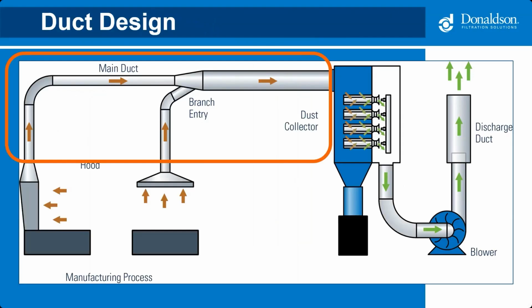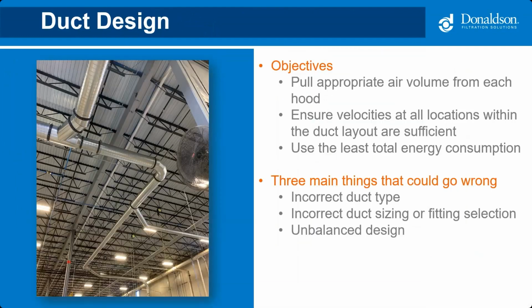Once we design the proper hood to capture the contaminant, the goal is to move the particulate to the filtration system through a series of ducts. A properly designed duct system should pull the minimum airflow required at each hood, should maintain the velocities required to move the material through the duct to the collector, and keep the material suspended in the airstream. And you should do this using the least amount of energy as possible and minimize any wear and tear on the duct components. A few common mistakes that I see quite often are the wrong duct type, the wrong size, and the system being unbalanced.